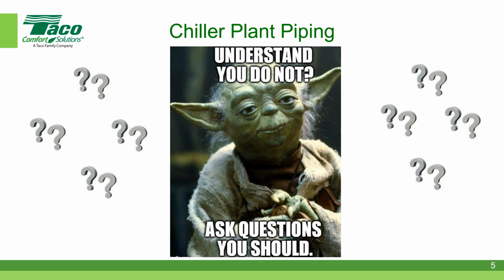Yeah, and I think glycol probably isn't used for that application, but maybe in a closed tower, a cooling tower located outside, it would probably be glycol that would be used in the northern states. Very good point. Yes, in an open cell cooling tower, you would not use glycol. We should just state that. But you're absolutely right, Brett. The closed cell uses glycol a lot, right?